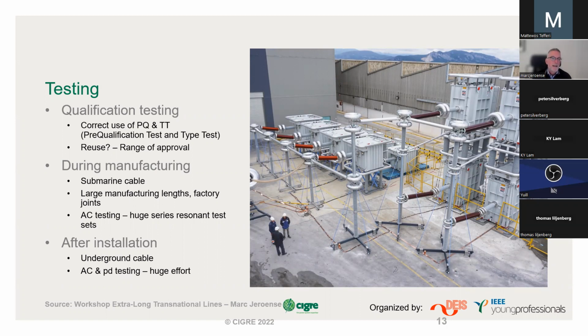And then we have after-installation testing. What one cannot do anymore is put an AC voltage on the whole cable link of maybe 500 kilometers. There is no mobile test set that can put this kind of voltage on this long a cable, which would demand so much reactive power.